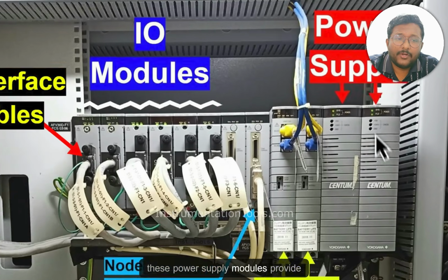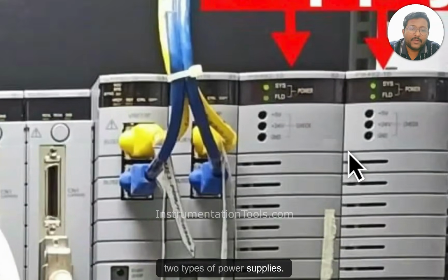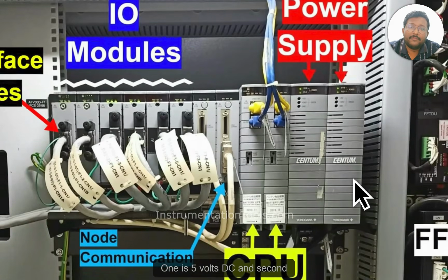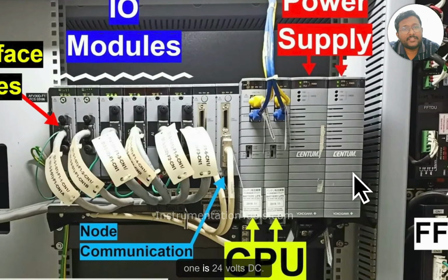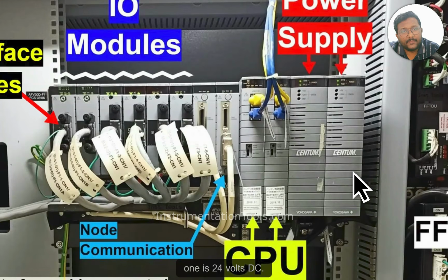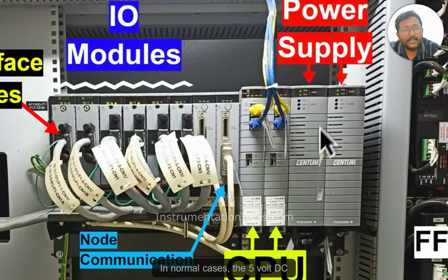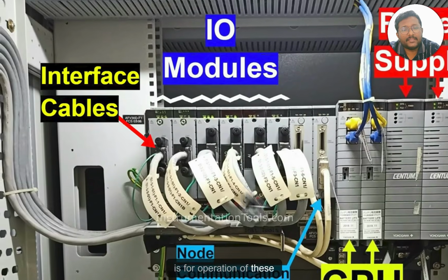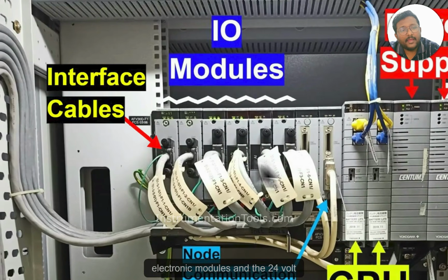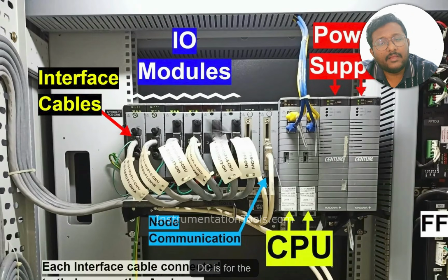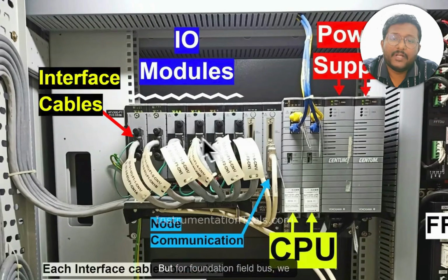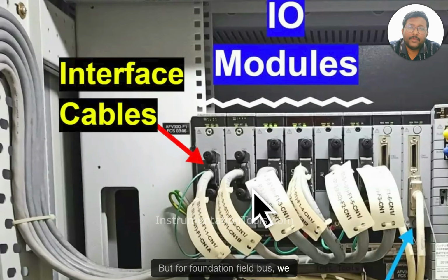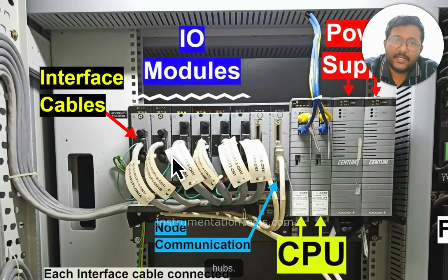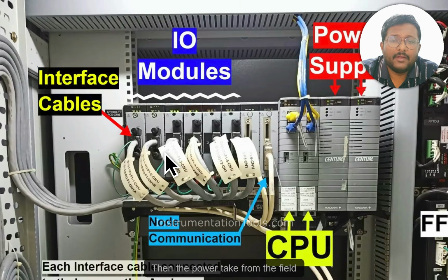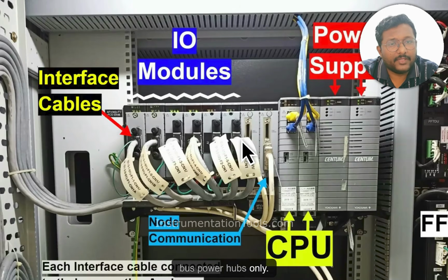These power supply modules provide two types of power supplies. One is 5 volts DC and the second one is 24 volts DC. In normal cases, the 5 volt DC is for operation of these electronic modules, and the 24 volt DC is for the field instruments. But for Foundation Fieldbus, we are providing another dedicated power supply to the fieldbus power hubs, right? Then the power is taken from the fieldbus power hubs only.